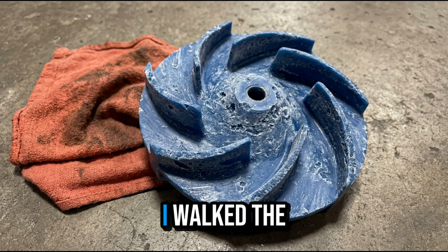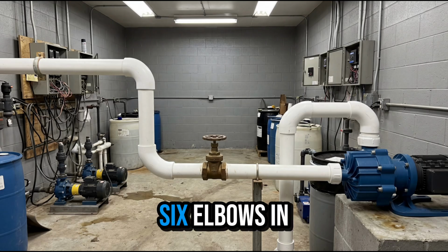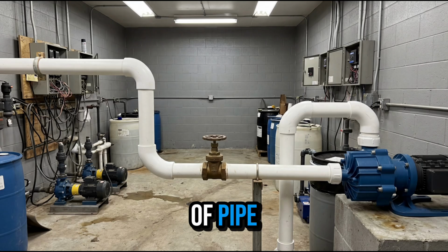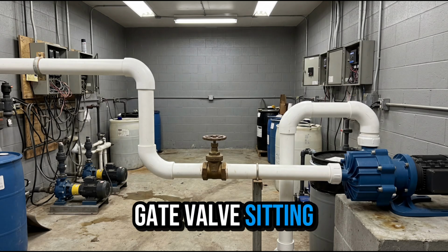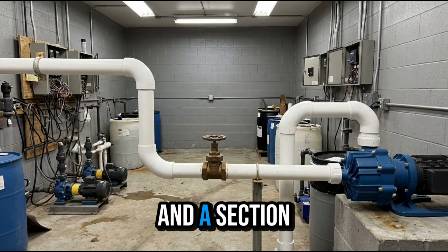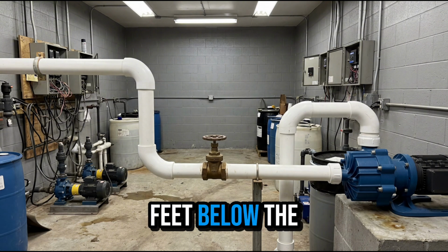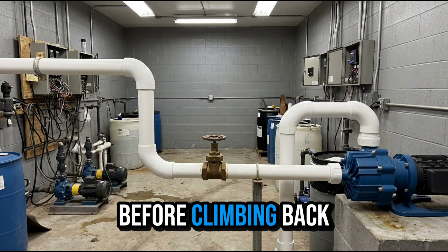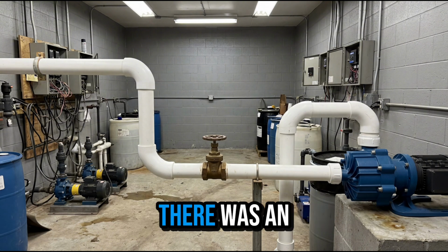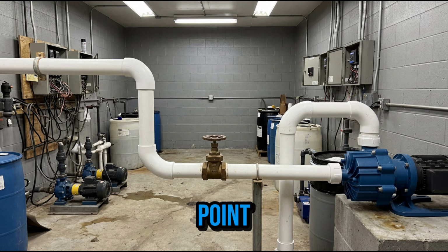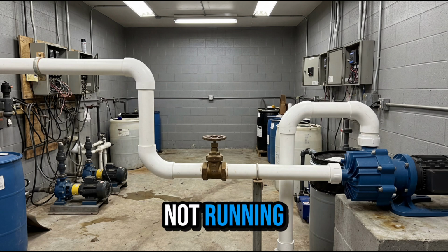Before I looked at the pump, I walked the suction line. 6 elbows in about 15 feet of pipe. A partially open gate valve sitting right in the suction run. And a section of suction pipe that dropped 2 feet below the pump center line before climbing back up to the inlet. There was an air pocket living in that low point every single time the pump was not running.